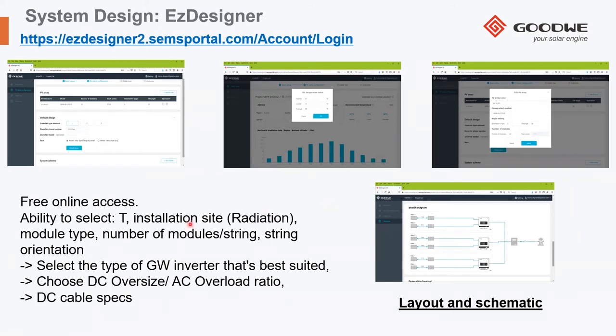In principle, you can select the temperature, installation site, the module type, the number of module strings, the orientation of the string. Then you can get as a first output the best type of GoodWe inverters that match better with your type of module. Then you can choose the DC oversize versus AC overload ratio. And you can also choose the DC cable specs. The result of this work gives you the layout and the schematic of your system. Very easy to use. The database of the module is not including all the modules because, you know, now the number of modules in the world is extremely high, but you can easily input yourself the data of the module to use this EZ Designer.